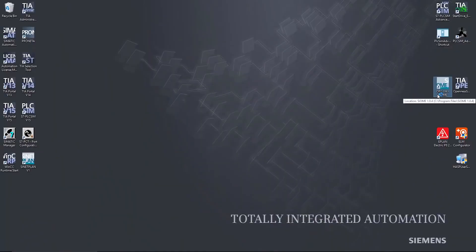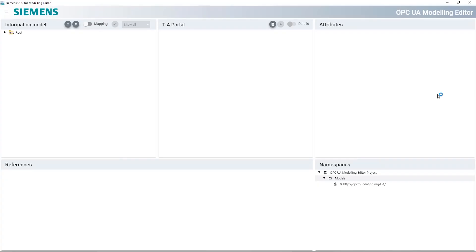Now we want to make this standardized data interface available to others. To do this, we'll use the integrated OPC UA server of the SIMATIC S7-1500 and the Siemens OPC UA Modeling Editor. With the OPC UA Modeling Editor, or SIOME for short, we can link the existing data from the S7-1500 to the OPC UA Companion Specification in just a few steps. The Companion Specification itself is a quasi-digital map based on OPC UA, which often uses long-established industry standards like OMAC PackML, for example.